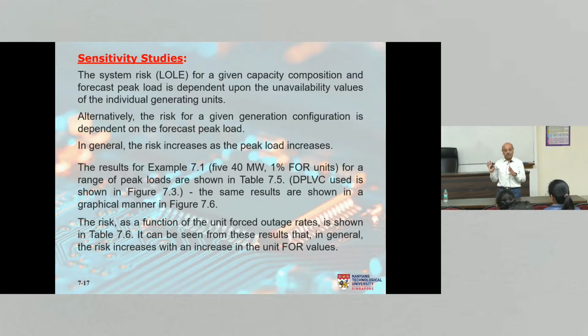So I'm going to show you some of them. Changes in peak load, changes in the unavailabilities of the generators. How do they impact the risk in the system? That is what we call sensitivity studies. That's the advantage of any research. Once you have the algorithm, once you have the program or whatever you are using, you just vary the parameters and see how it impacts the output. So that's what I'm going to share with you.